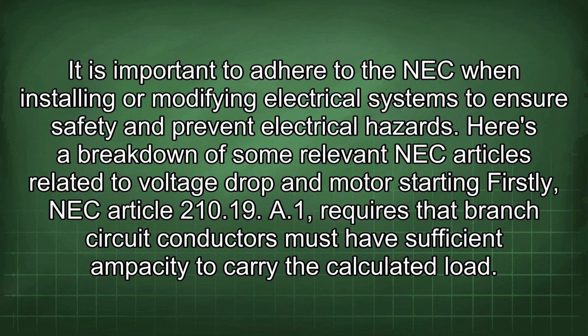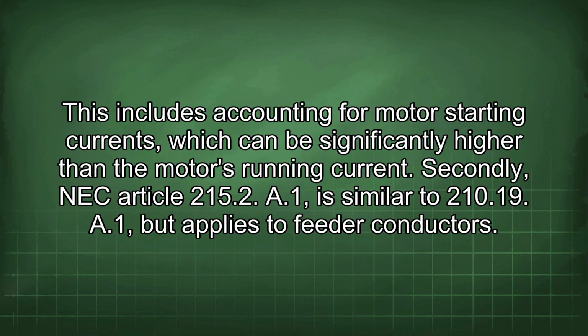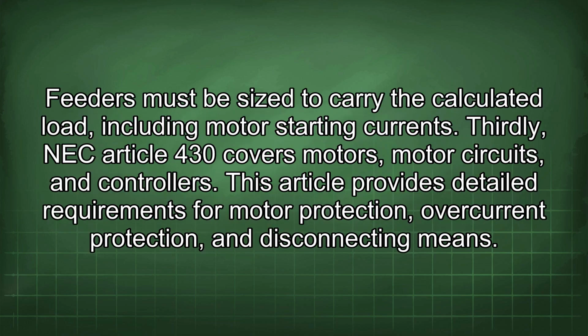Firstly, NEC Article 210.19(A)(1) requires that branch circuit conductors must have sufficient ampacity to carry the calculated load. This includes accounting for motor starting currents, which can be significantly higher than the motor's running current. Secondly, NEC Article 215.2(A)(1) is similar to 210.19(A)(1) but applies to feeder conductors. Feeders must be sized to carry the calculated load, including motor starting current. Thirdly, NEC Article 430 covers motors, motor circuits, and controllers. This article provides detailed requirements for motor protection, overcurrent protection, and disconnecting means.